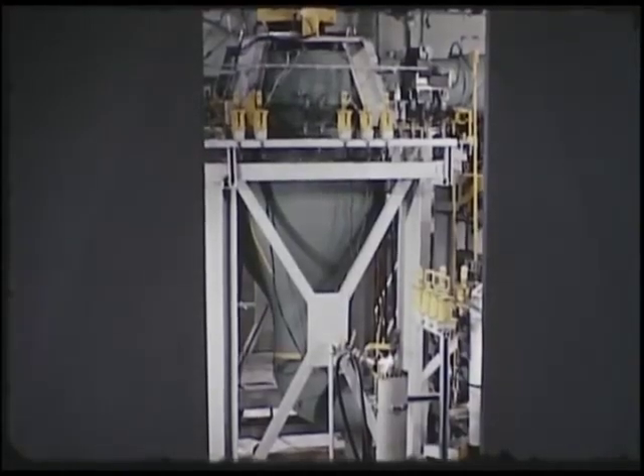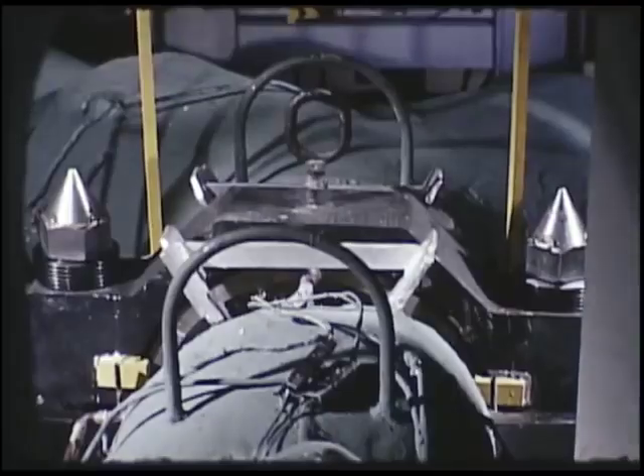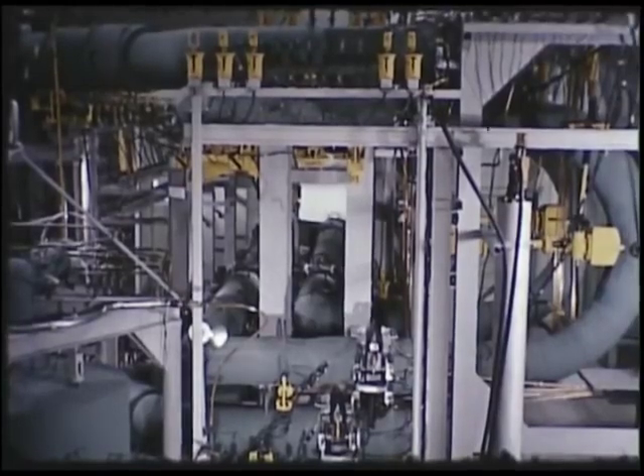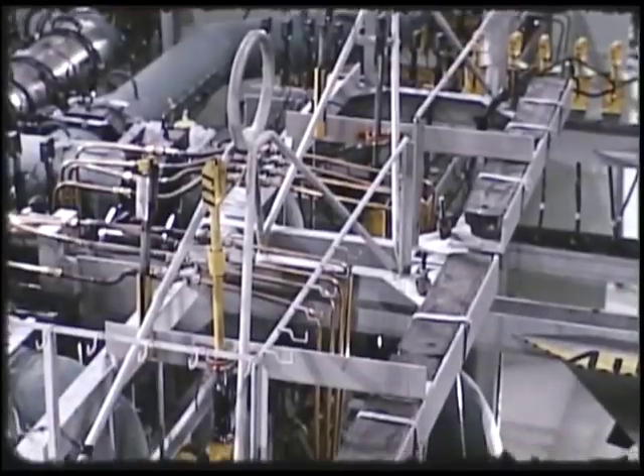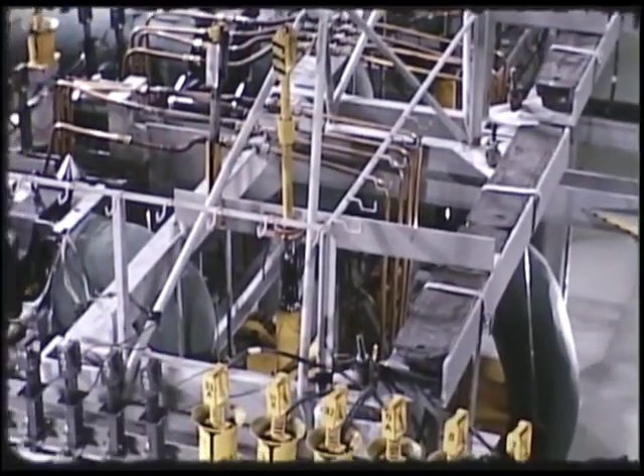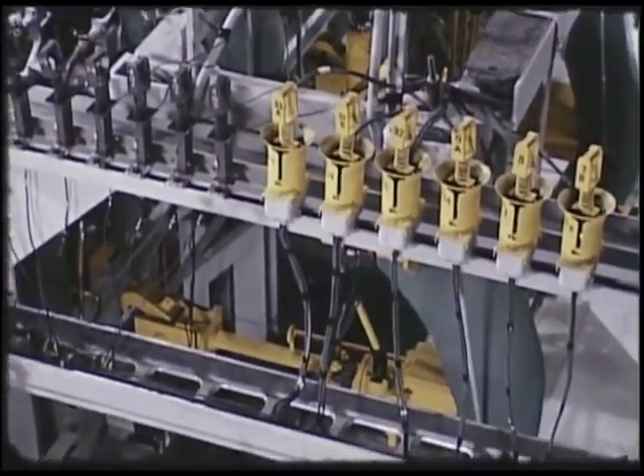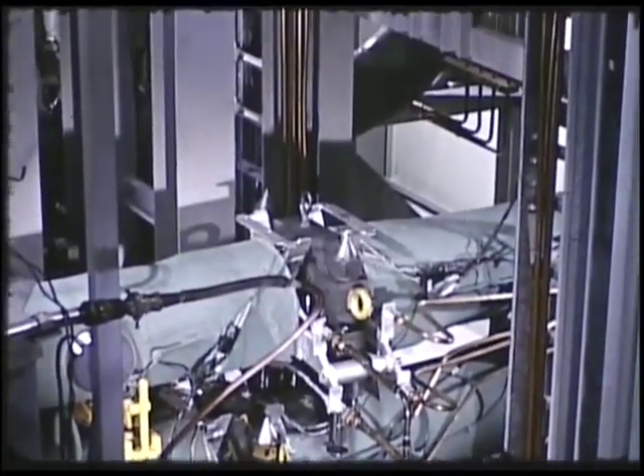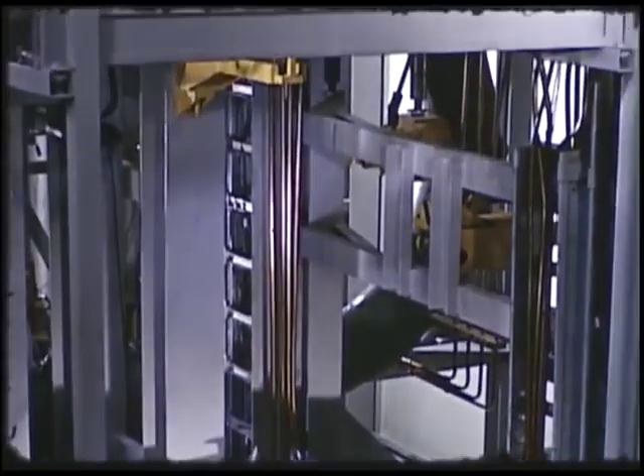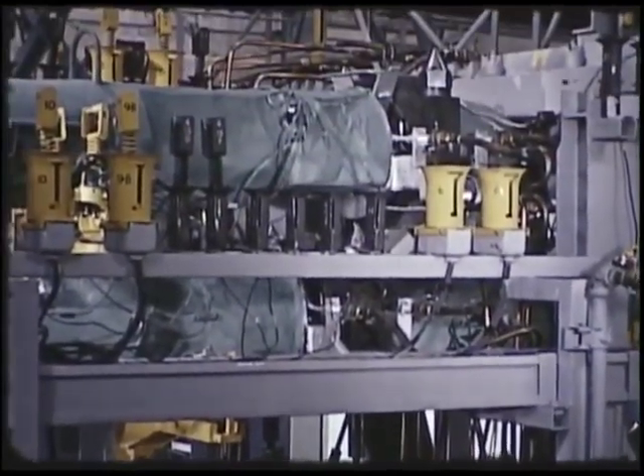The reactor is connected to the primary piping circuit by two 6-inch mechanical joints of the freeze flange type. Two heat exchangers of the tube and shell type are arranged in semicircular shape. Each is suspended from a dolly that is free to move laterally during expansion of loop piping and during replacement. Both heat exchangers are connected to the primary and secondary systems by four 3.5-inch freeze flange mechanical joints.